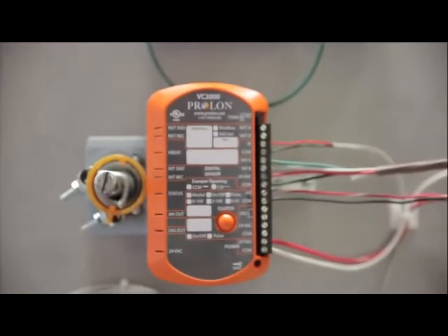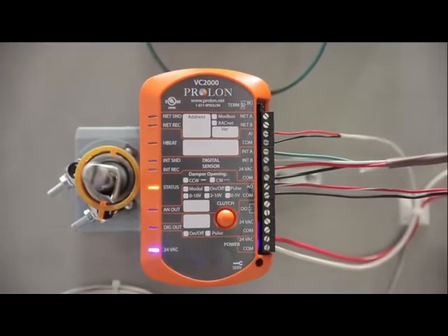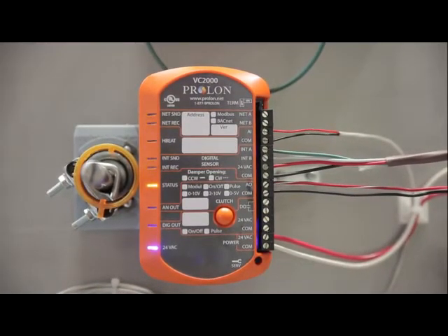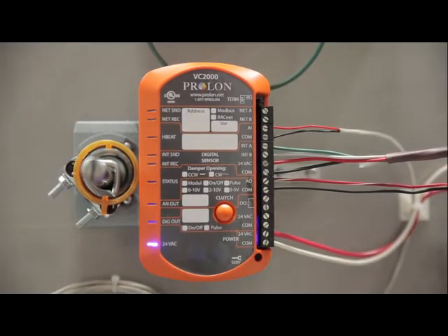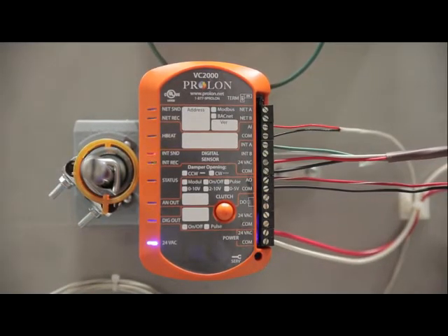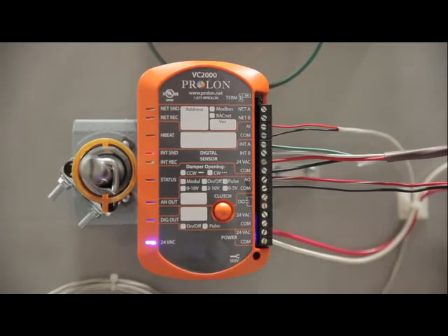Upon initial power up, various pilot lights on the VC2000 illuminate to confirm different functions of the controller. The blue power and heartbeat lights confirm normal operation. The yellow status light indicates the damper opening direction.